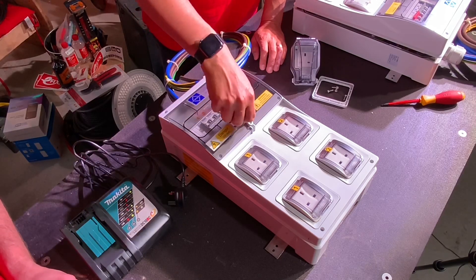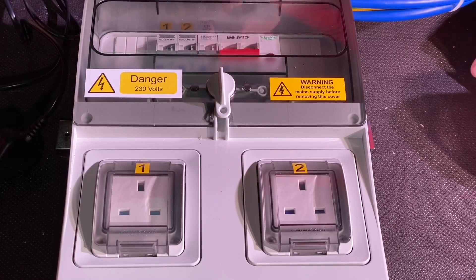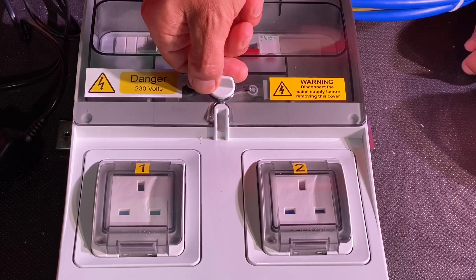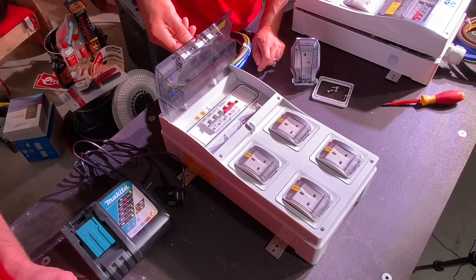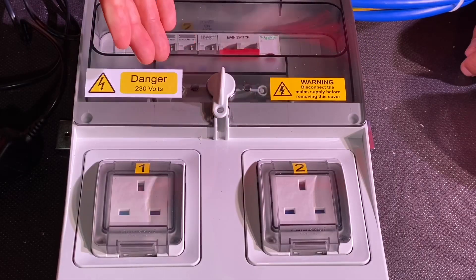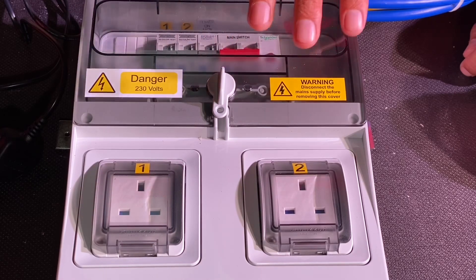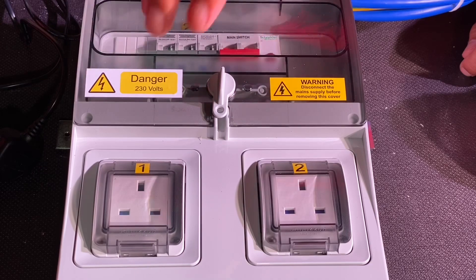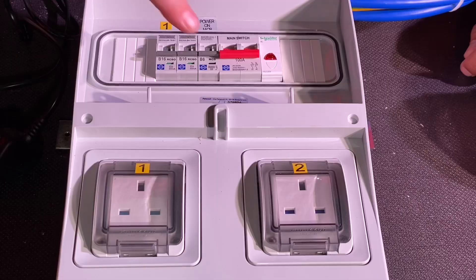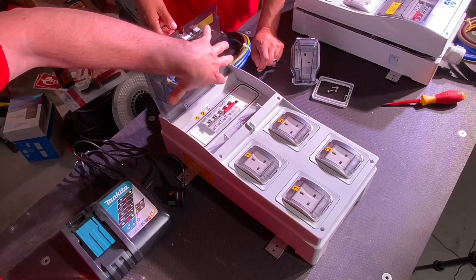Starting with the important IP rating - the enclosure is IP66. If you haven't seen the IP ratings video, check it out. IP66 means jets of water from all directions and clouds of dust from the desert, so the chances of getting water in here are pretty slim. One thing I really love about the Lewden Top Tier range is this mechanism - a nice smooth action. A lot of enclosures, once the covers are on and the seal has gripped, you end up wrenching the thing off the wall to open it again. This is just lovely.